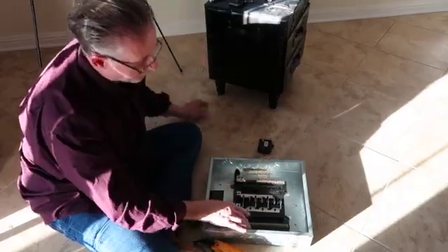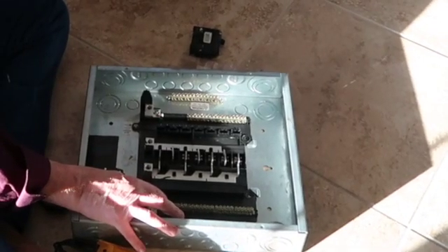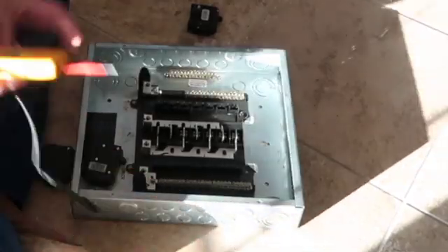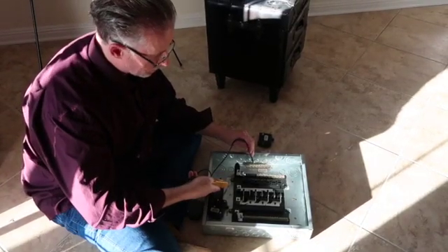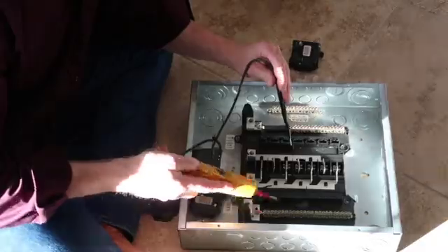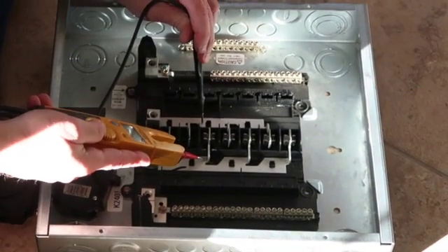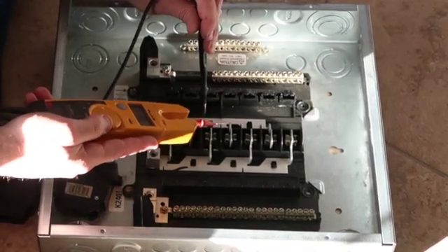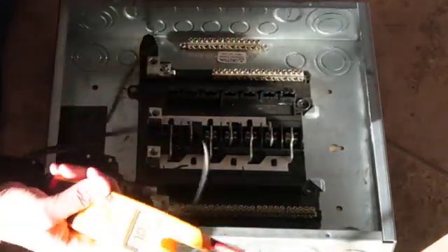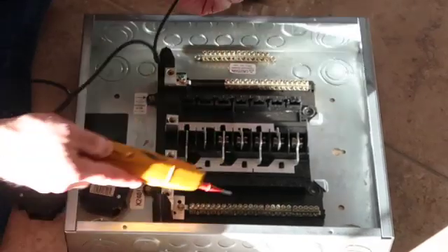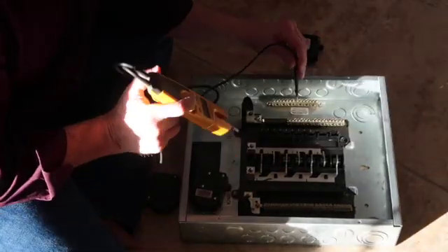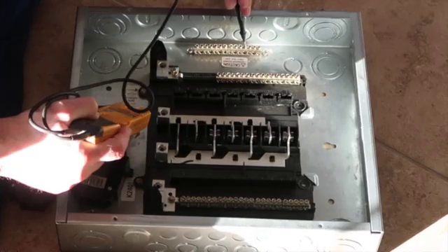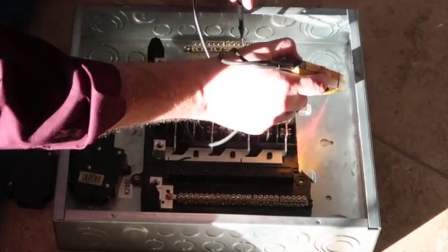Now what this stuff is for, this is for your neutrals which is your return. And then you would have your wire going from here to a ground rod in the ground. And these are for your grounds. Here's your ground wire right here. And this is for your neutral wires right here. If you notice there's no continuity between these two. And the reason being is if this is 120 and this is 120 and there was continuity, then what would happen is I'd have a direct short between two hot legs and it would blow up as soon as I turned on the power. There's no continuity between here and either one of these because once again this is a neutral and it's going to be grounded. These right here are for your equipment grounds. These have continuity to your panel. Right now I'm hearing a beeping noise. That means that this is connected to here, it has continuity.